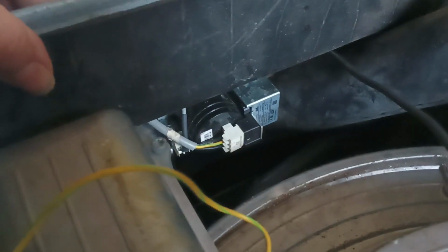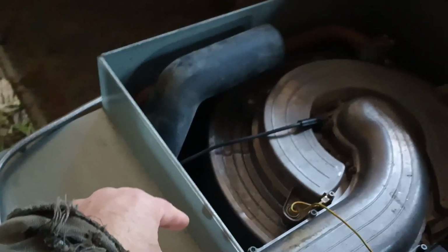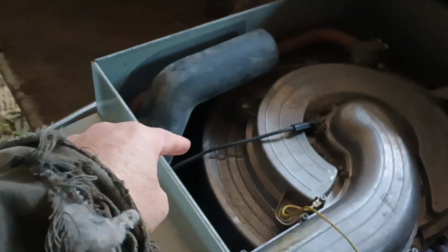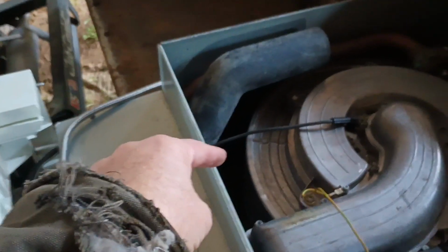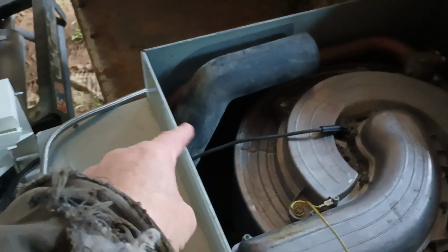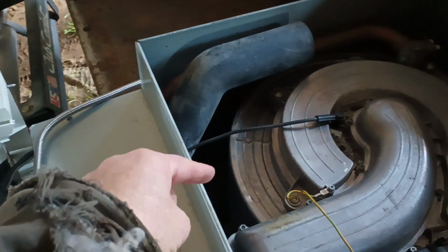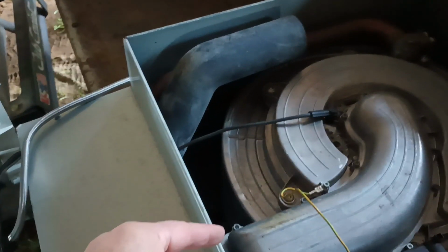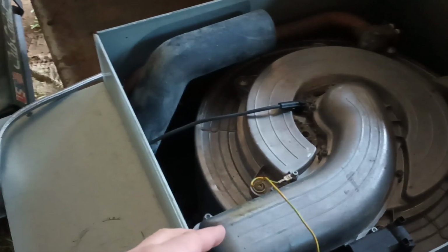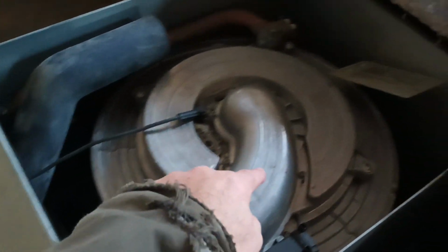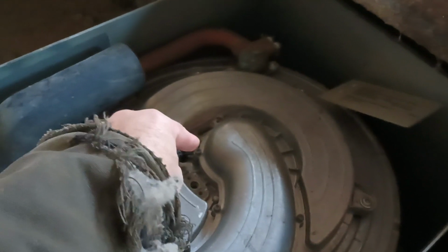There's a combustion fan down here. We're looking at the boiler kind of upside down and backwards now. So this little metal pan will come off. There's a combustion fan inside. The combustion fan is attached to a negative pressure gas valve that draws gas through the gas valve, gets pushed into the fan, does primary air mixing and fuel mixing, pushes it up through this duct, and then there's a burner on the back side of this.